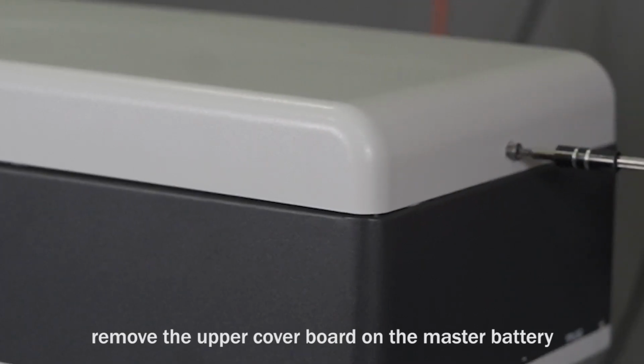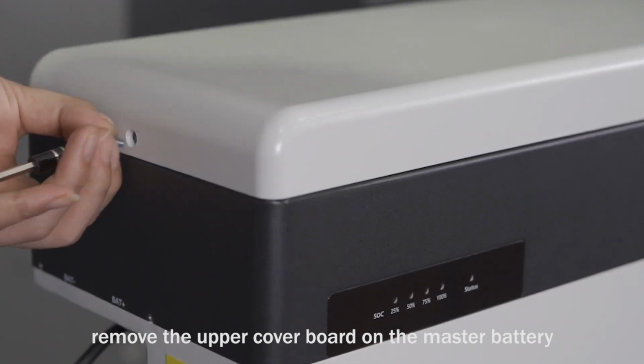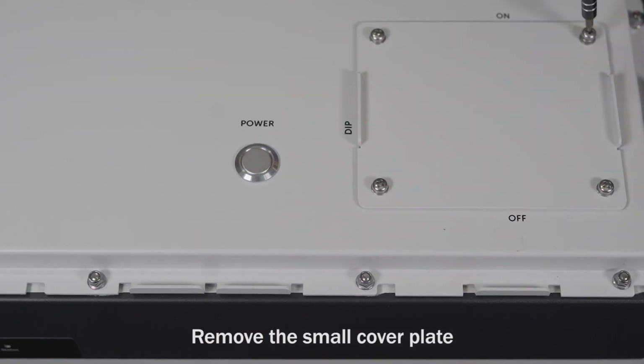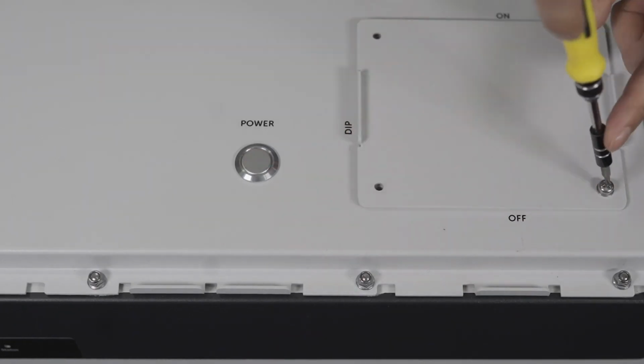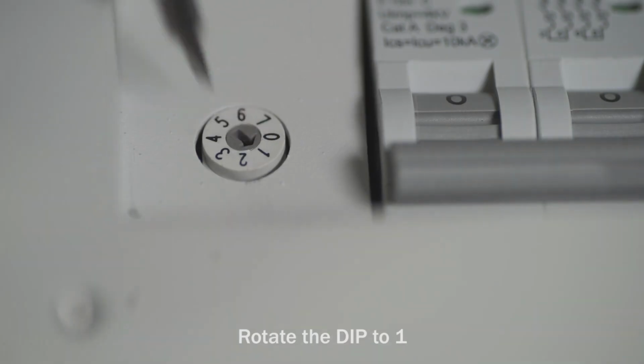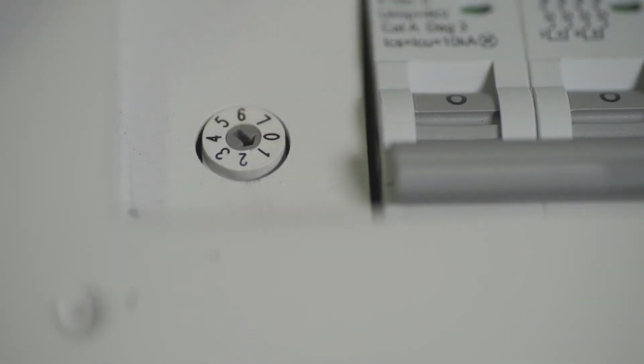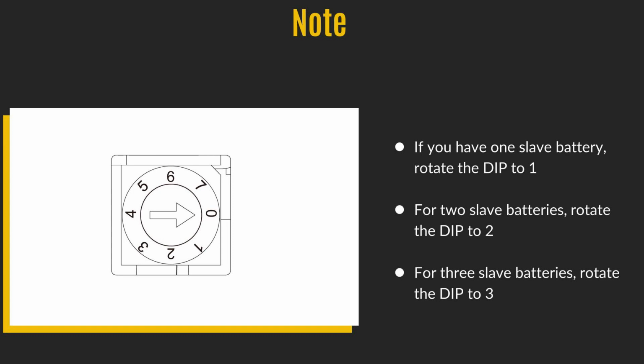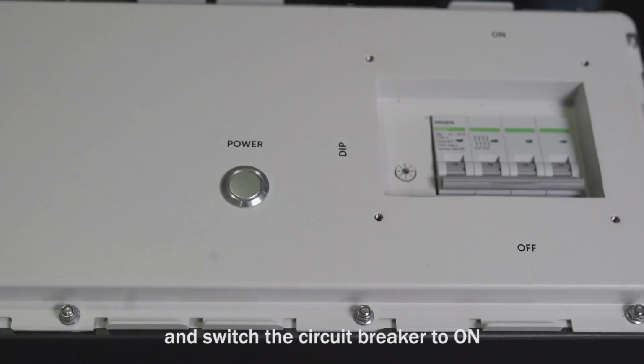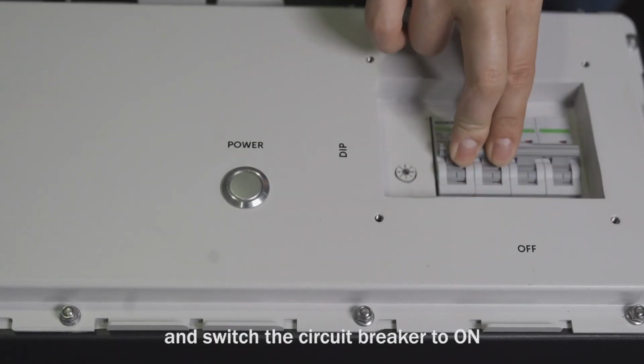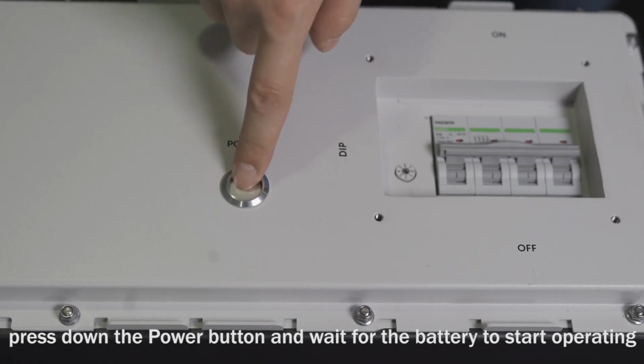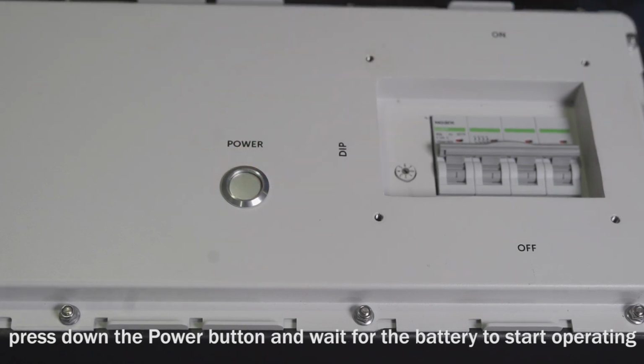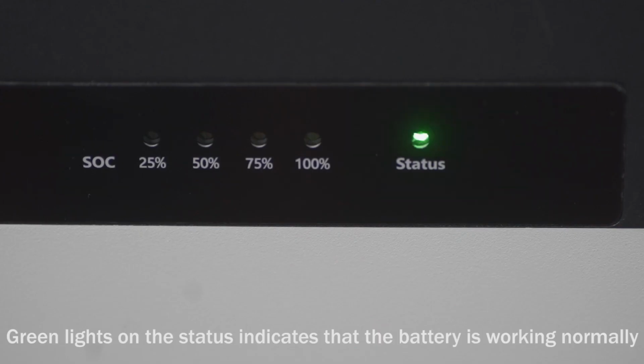Remove the upper cover board on the master battery. Remove the small cover plate. Rotate the dip to 1. And switch the circuit breaker to on. Press down the power button and wait for the battery to start operating. Green lights on the status indicates that the battery is working normally.